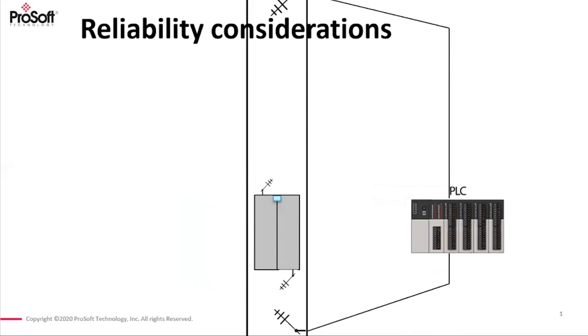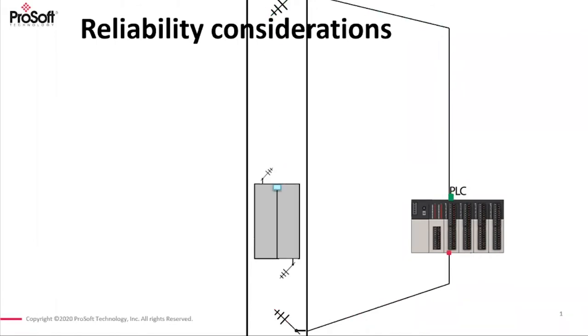Another thing about tolerance is data drops. Wireless systems have a multitude of variables, a multitude of stuff that will affect how the wireless system operates. So for our elevator, which we say cannot tolerate a single packet loss, we would recommend a design that utilizes Parallel Redundancy Protocol, or PRP. And you would of course need radios that can accommodate that. With PRP, you can have traffic replicated on two independent communication paths, thereby reducing the probability of a packet loss. The PLC will accept the first good packet it gets and discard the other, thereby providing the communication system with a fallback if one link gets disrupted somehow.